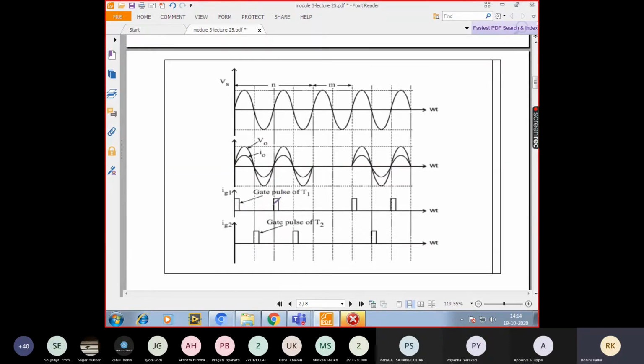That means whenever the device gets a positive or negative half cycle, say at omega t equal to 0, pi or 2 pi, I have the gate pulse for n cycles. Whereas for m cycles where the switch should be off, I keep the gate current off for both positive as well as negative half cycles, so the device will not be triggered.